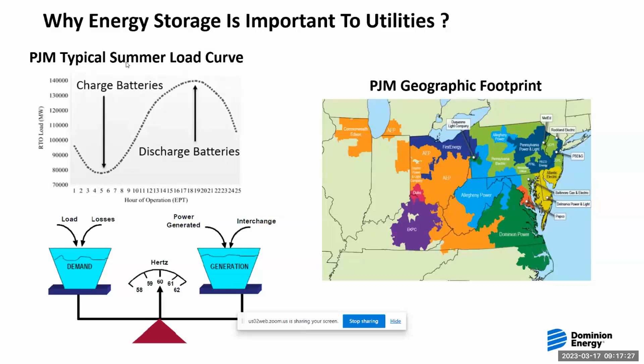Dominion Energy got into battery storage with the passing of the Grid Transformation and Security Act of 2018, which called for Dominion Energy to install its first 30 megawatts of energy storage in our service territory. At that time, we developed a pilot program seeking to improve reliability of our bulk electric system and our distribution system, improve and increase the integration of different types of renewable energy resources, defer the investment of infrastructure—specifically generation, transmission, and distribution infrastructure—and reduce the need for additional generation during times of peak demand at that peak point of the PJM load curve. Thus far, Dominion has deployed 3 pilot projects on our distribution grid, totaling 16 megawatts.